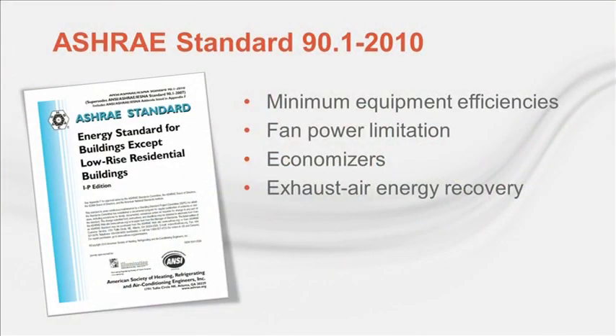While codes vary by jurisdiction, today we'll focus our discussion on ASHRAE Standard 90.1, since it's the basis for most model codes. Murph? While there is certainly a long list of requirements in Standard 90.1, I'm going to discuss just a few of the common questions we get about complying with the standard when using a VRF system. I'll start with the minimum equipment efficiencies and then talk about the fan power limitation, economizers, and exhaust air energy recovery. And as the slide indicates, I'm going to use the 2010 version of the standard for this discussion, since it's the version used in the current model codes as well as the newest version of LEED. But if something has changed in the 2013 version, I'll be sure to point that out too.